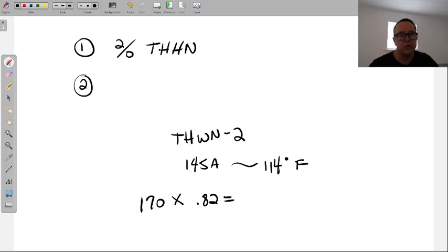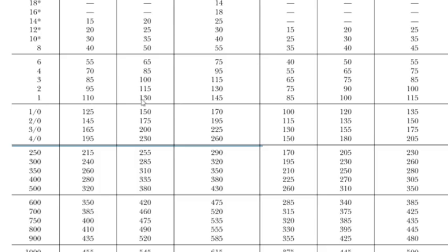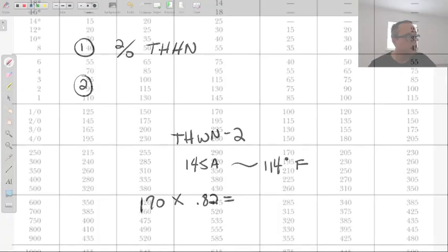All right, just to start somewhere, I start with a decision that's considering the fact that this wire is going to have the amperage reduced by a little bit. Now, I'm not going to start way up high. I'm not going to start with a 3/0 because 225 is just much larger. I'm looking for minimum. So I'm going right to that 1/0, which is 170.